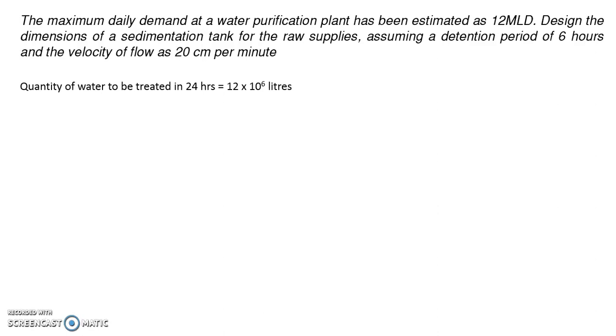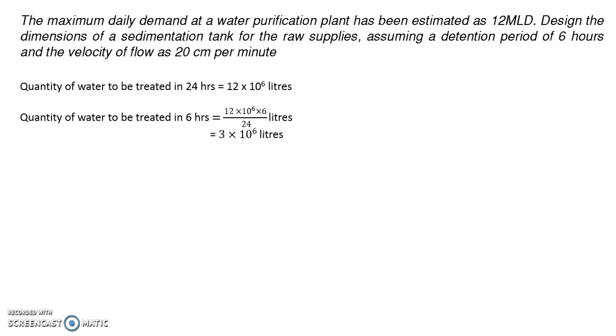The quantity of water to be treated in 24 hours is 12 × 10⁶ liters. For one hour it is 12 × 10⁶ divided by 24 liters. The quantity to be treated in six hours — the detention period — is (12 × 10⁶ / 24) × 6, which is around 3 × 10⁶ liters, i.e., 3 million liters.